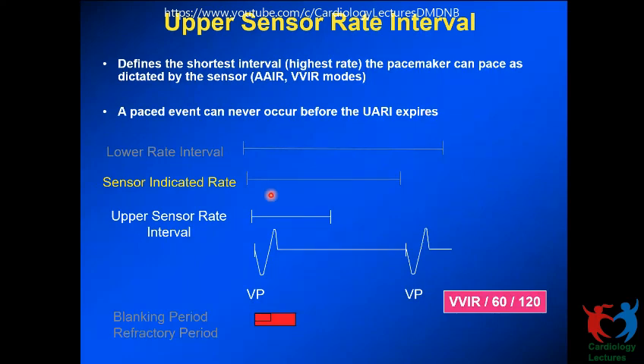Now this patient is running. The sensor is vibrating maximally, and here you have put a limit, so the timing interval will be 500 milliseconds. So it varies between that. This is for the ventricle. When you deliver a pace, whether it's a sensor indicated rate or otherwise, it starts the refractory period and the blanking period, for the same reason. And if there is a ventricular intrinsic sensing right after this, it's going to reset the clock. If it is at the upper sensor rate, then the clock running at that time will be 500 milliseconds according to this programming.